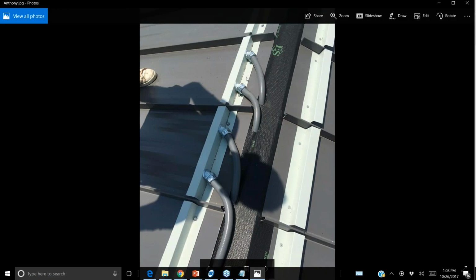photo where we have the metal roofing purlins, and then DC wiring has to be in metal conduit. And so we had to use metal fittings because we couldn't use plastic fittings. It's DC wiring going through the roof at that point. And this is not a non-metallic flex conduit. This is a metallic flex conduit. And you can kind of see the bending radius is similar to what a field bended conduit would look like. So we're not gaining much in terms of bending radius. In fact, we couldn't just go straight through the Z purlin into the rooftop because this bending radius was physically required. It's not like you could just give it an extra oomph that would break it. You're not allowed to install broken conduit on your job. We had to give it this 45-degree tilt.